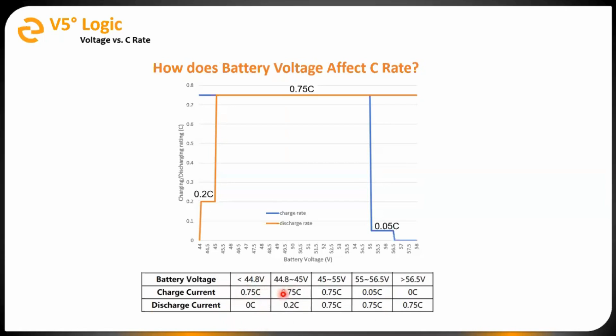As our voltage increases, we exceed 55 volts. We're getting closer to the top end of the BMS. The battery charge current is going to start to limit itself until it'll basically prevent any charge from coming through if the voltage is high enough. So with higher voltage, we're seeing our charge rate decrease, but our discharge rate stays the same. The opposite happens at the other end of the chart here. As our voltage gets lower, the BMS is going to prevent you from discharging. So our discharge current actually goes to zero, whereas the charge current remains at our full 75 amp value.